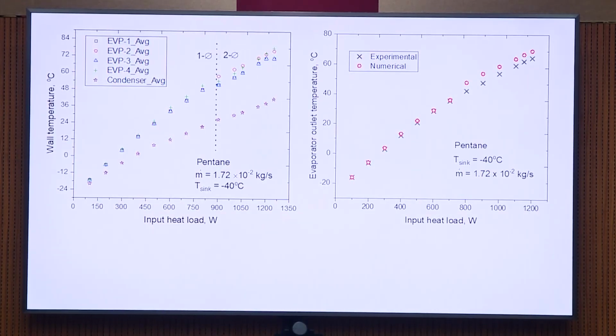This is the result for the evaporator temperature. If you see, the average evaporator temperature at 1 kilowatt is roughly up to 65 degrees. This is what we desire, that is the operating temperature, and we were able to achieve it. And the delta T between both will be around 15 to 20 degrees. The right side picture shows the comparison between numerical and experimental, and we got very good agreement between both.